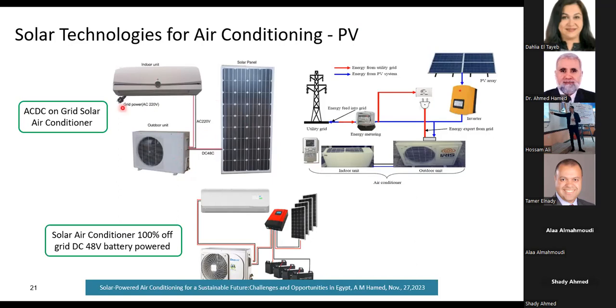In the first one, on the left side, this is called an AC/DC on-grid solar air conditioner, in which the current coming from the PV feeds the outdoor units, and then the signal goes to the indoor units, which is powered by the electricity from the grid. The lower one is a completely off-grid DC 48 PV battery system. In this case, all the energy collected from the PV is either supplied to the system or stored in the battery to use in the case of there being no solar energy.